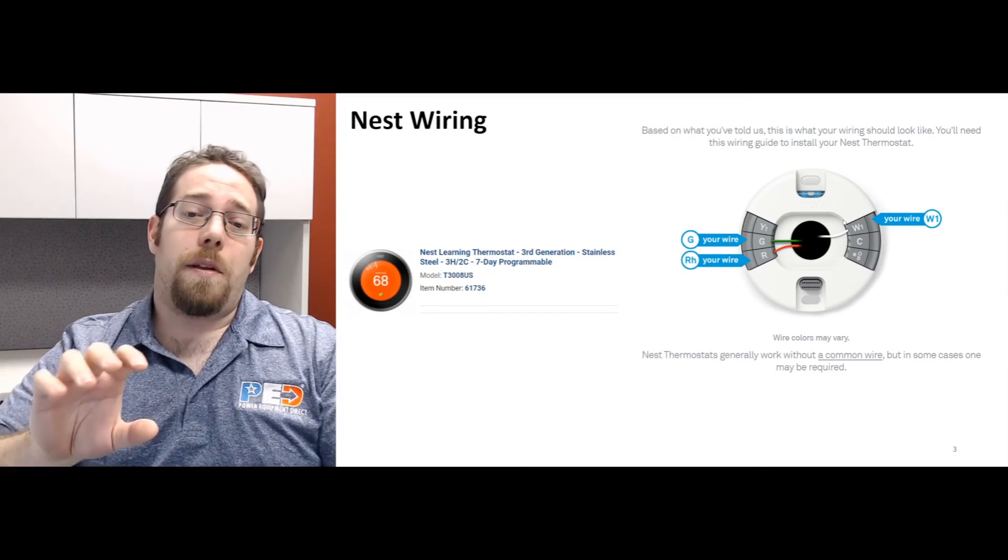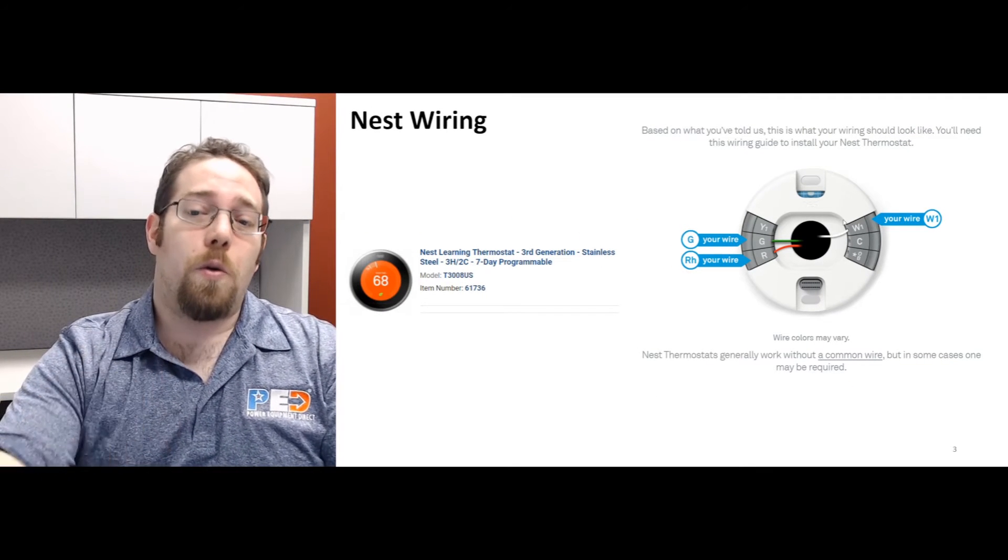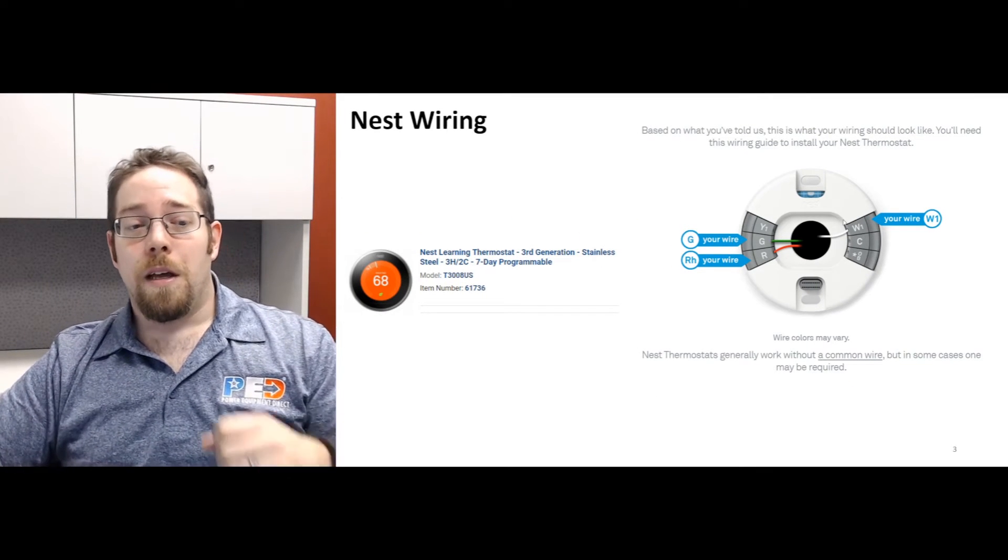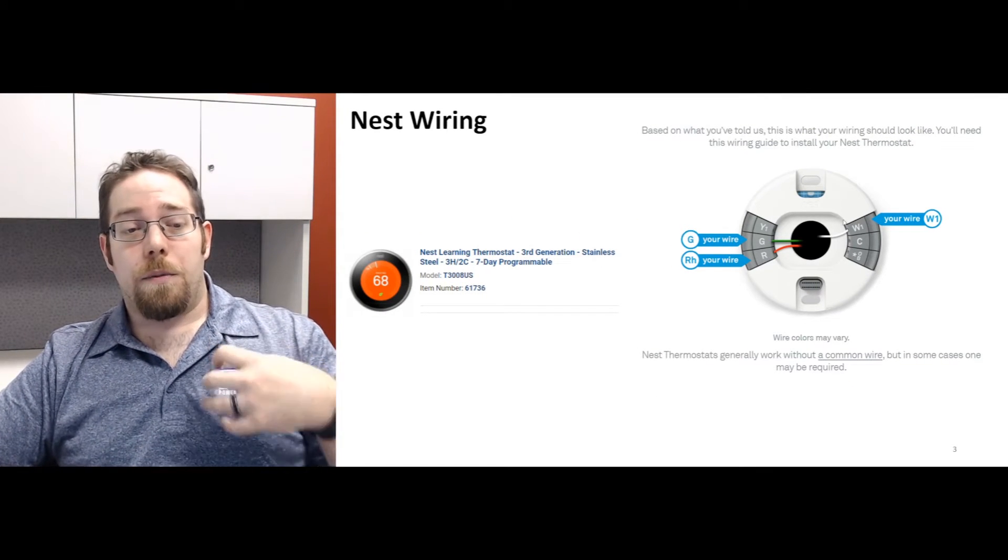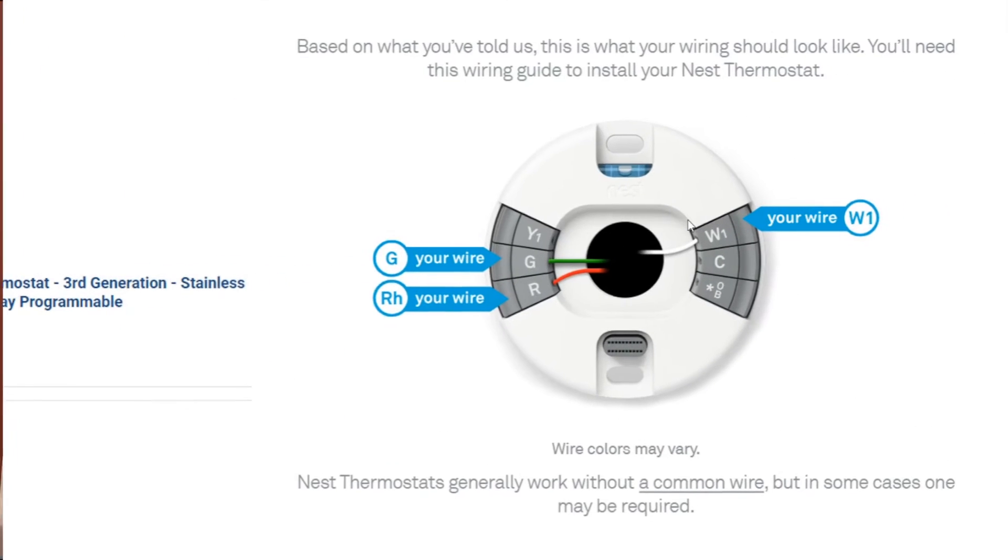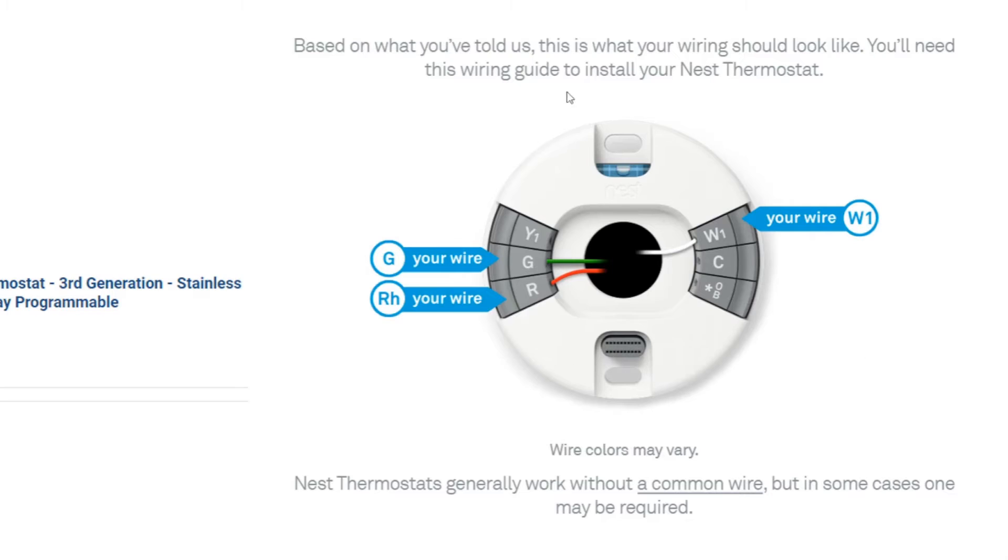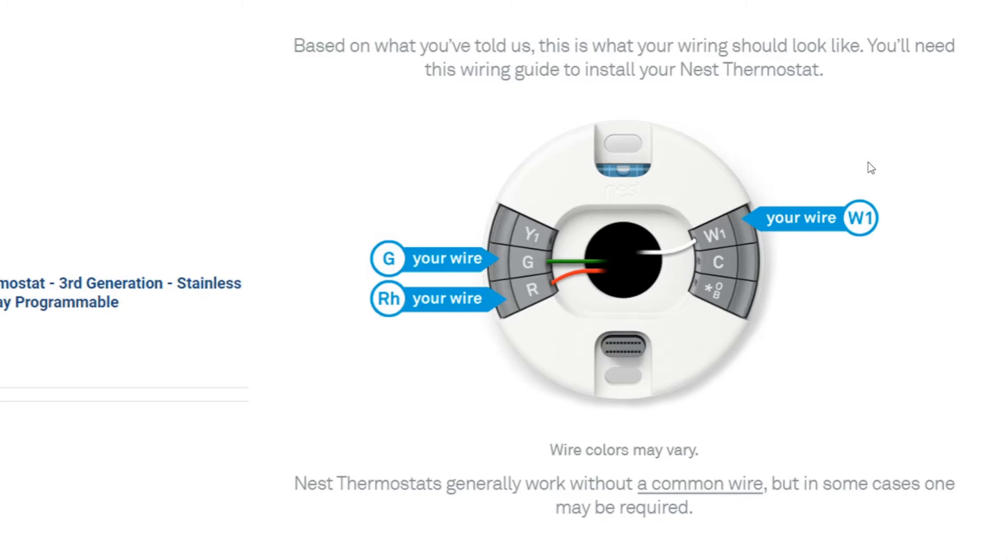But typically if you have the old thermostat, and what I have listed on here is the old original thermostat, because some of the newer thermostats such as the one that we do have, third generation, will have a whole bunch of more connecting points. It'll say W2, it'll say C, it'll say R, RH, and a bunch of other stuff. I want it to be as simple as possible for you right now. Once again, the same thing as those other thermostats, you're connecting an RH, a W1, and if you want the fan to work that's gonna be a G.